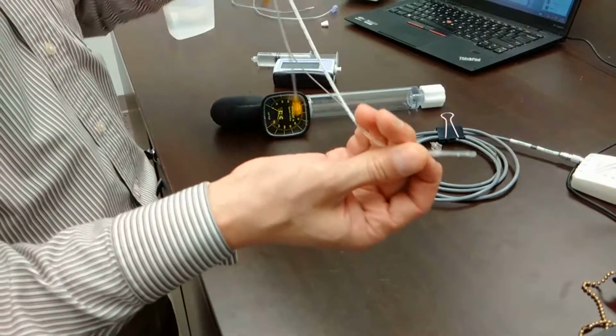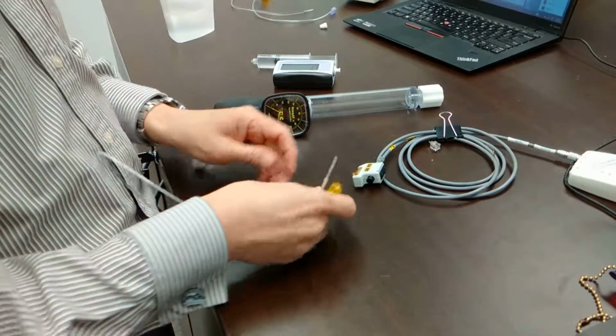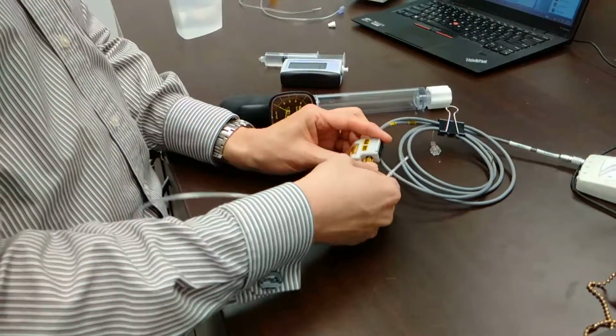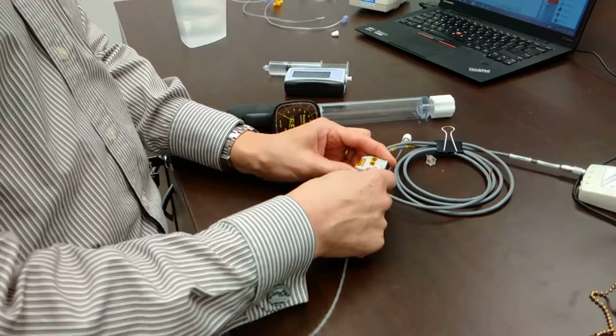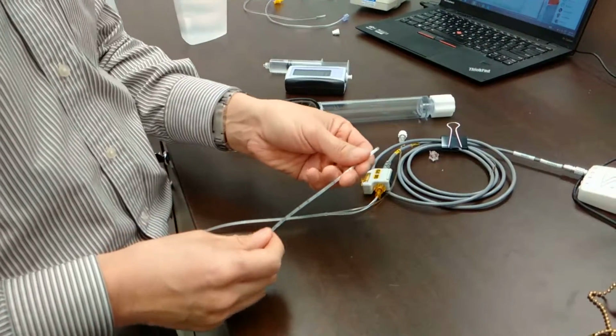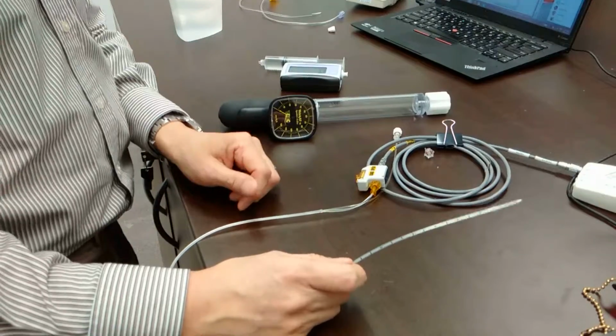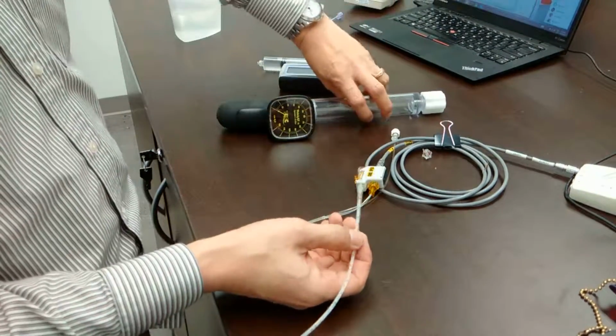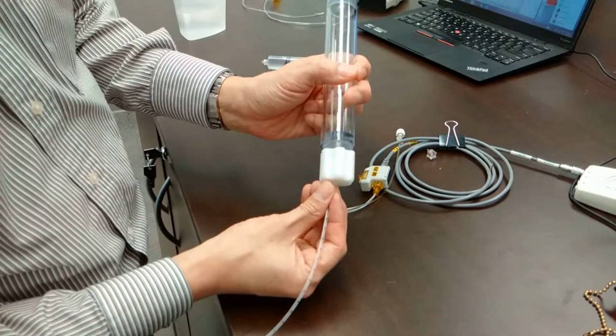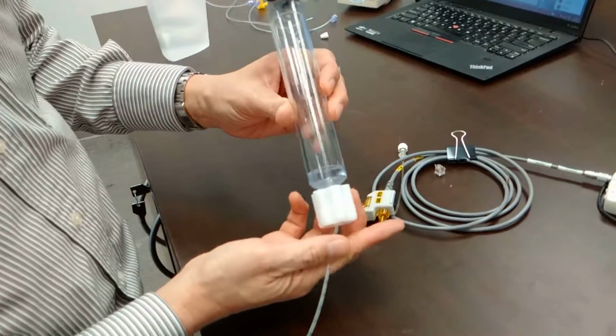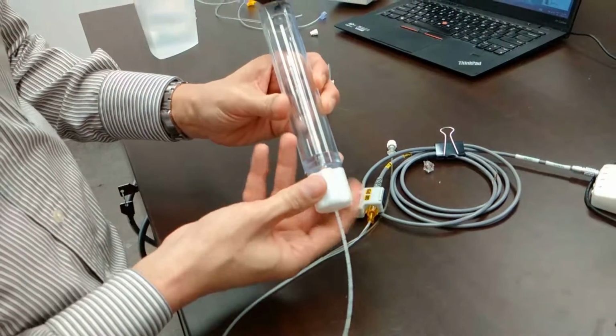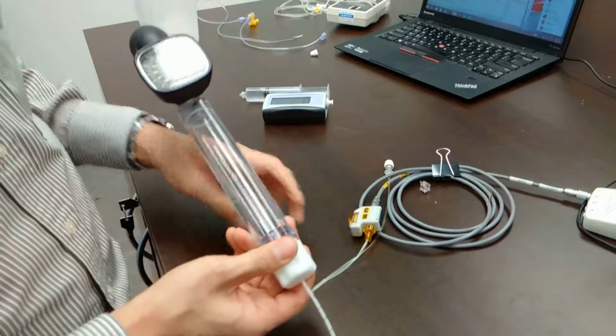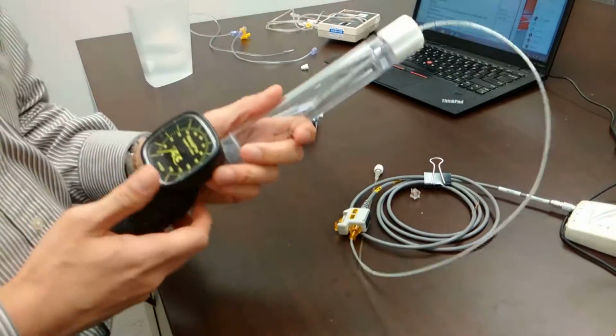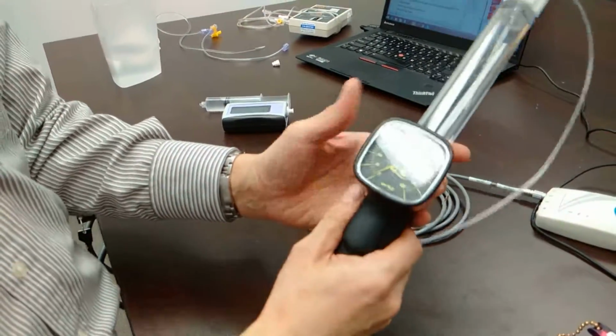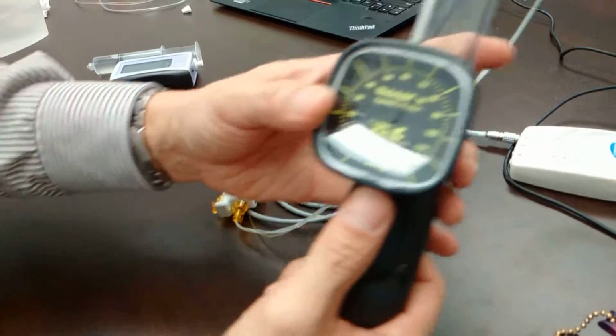Essentially, you will need a catheter, and this catheter can't be used on the patient. Once you use it and put it inside that chamber, it doesn't remain sterile. So in this situation, you will put it inside this chamber and use this locking nut to close it. You hit the charge position, and now you've got centimeters of water on this dial. We compare it with the readings you have on the screen.